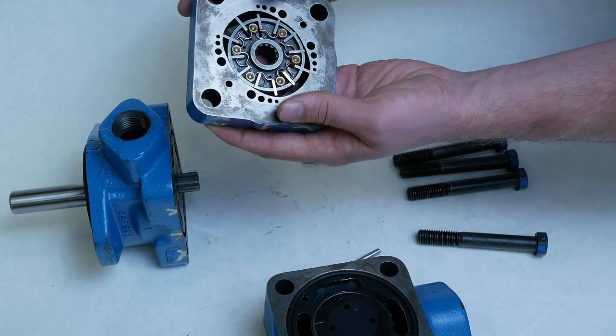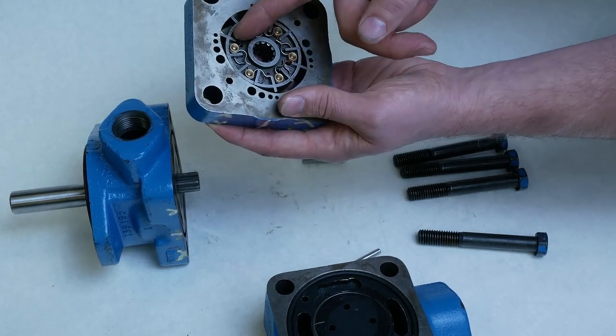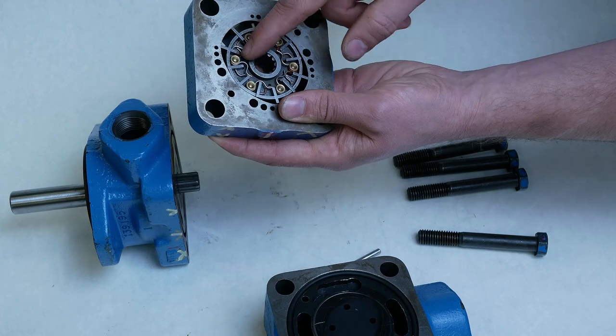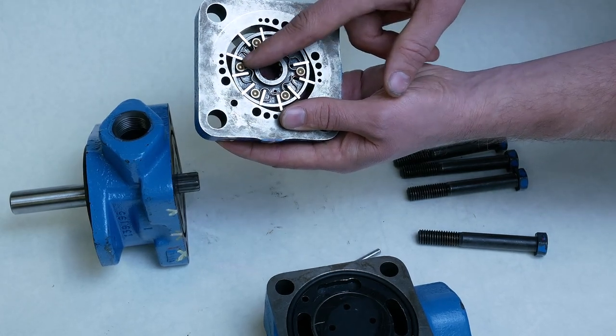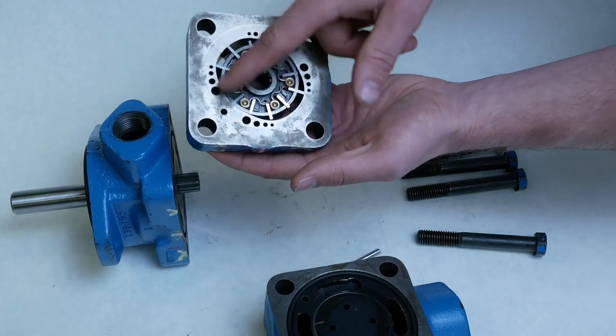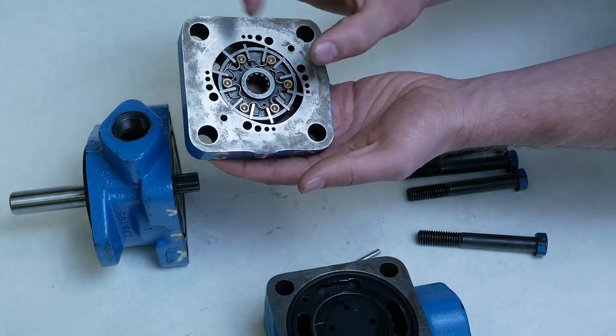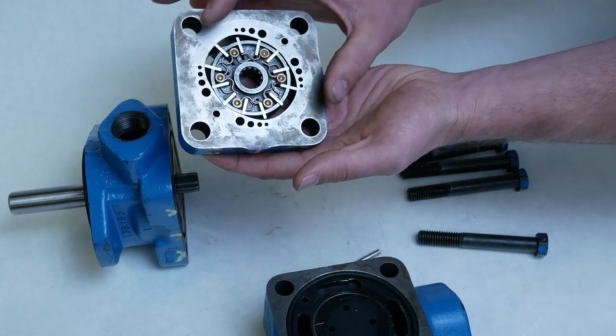And I'll show you that here, where we'll take a seal pick and pull these back so that this leg of the spring is actually pushing on the backside of the vane. Otherwise, each of these vanes should be pushed out against the cam ring.